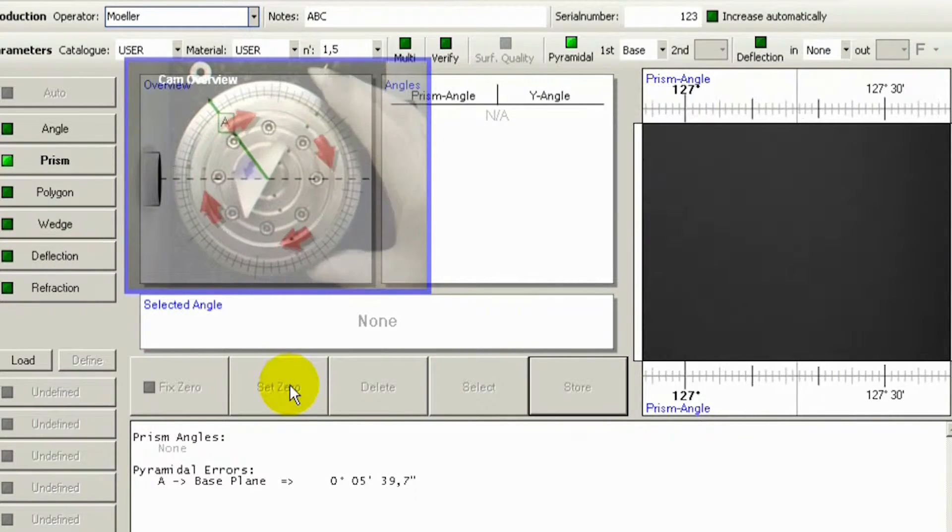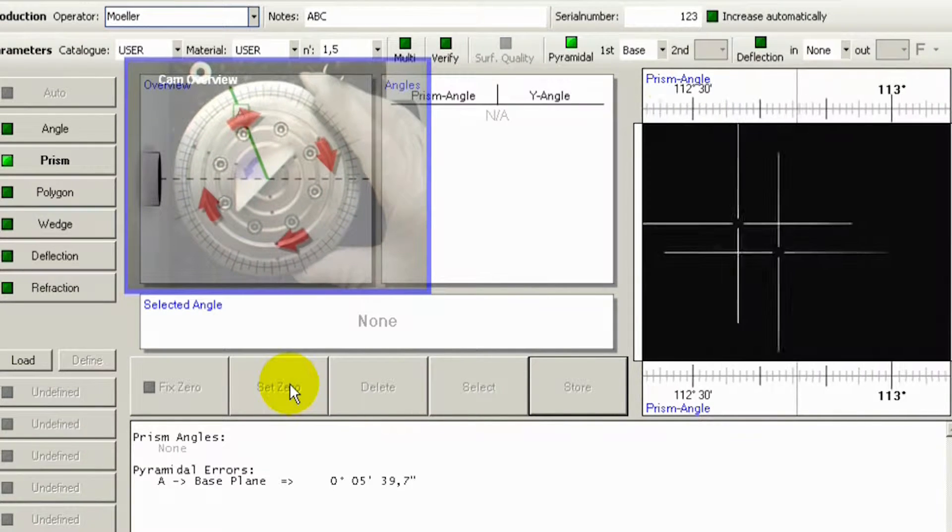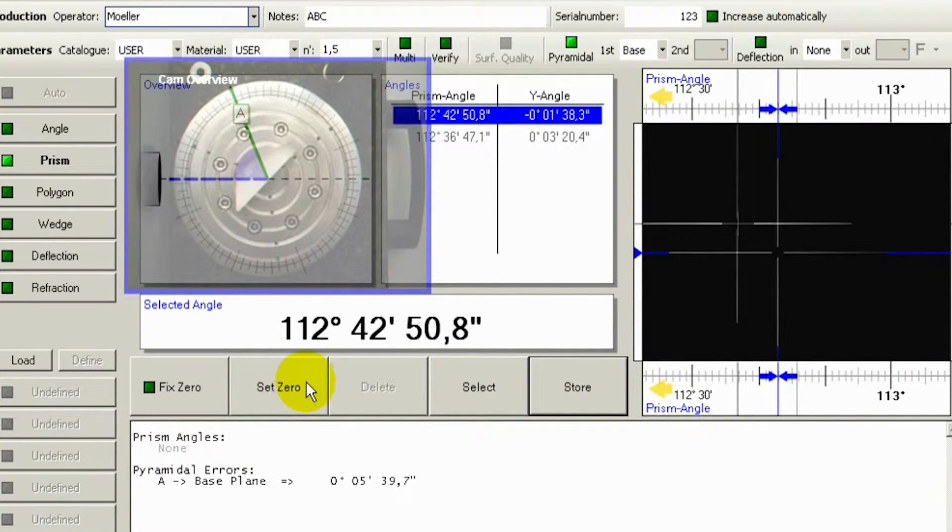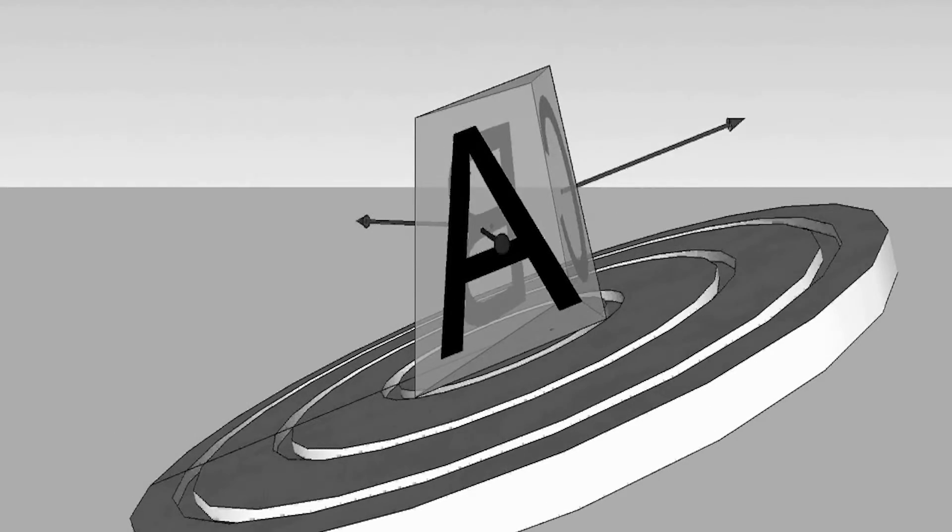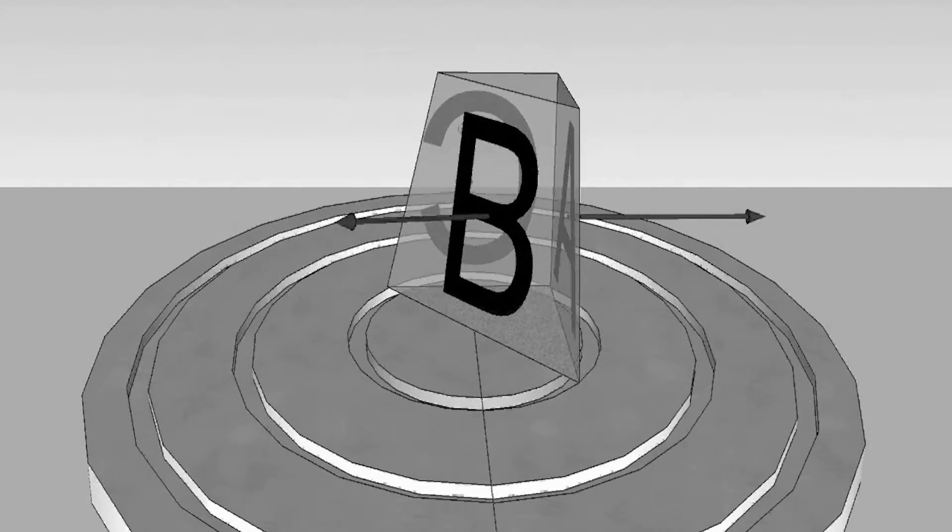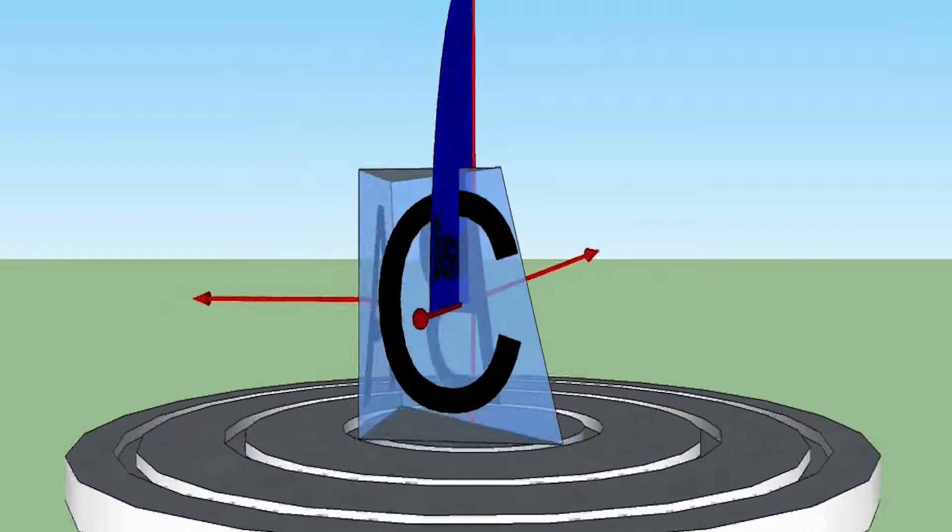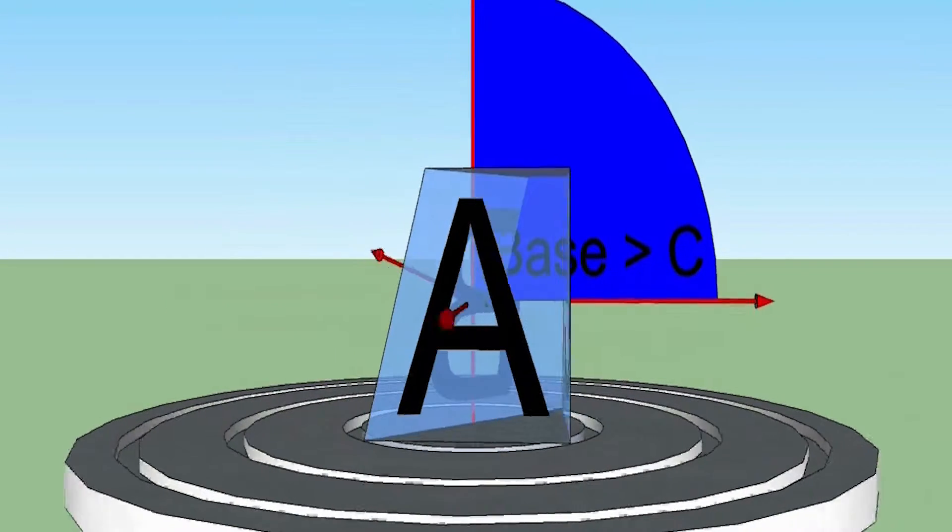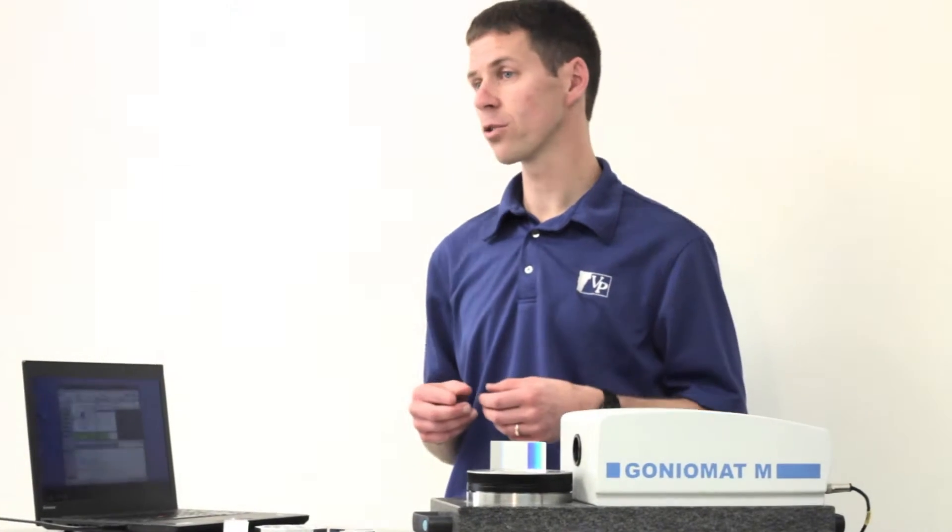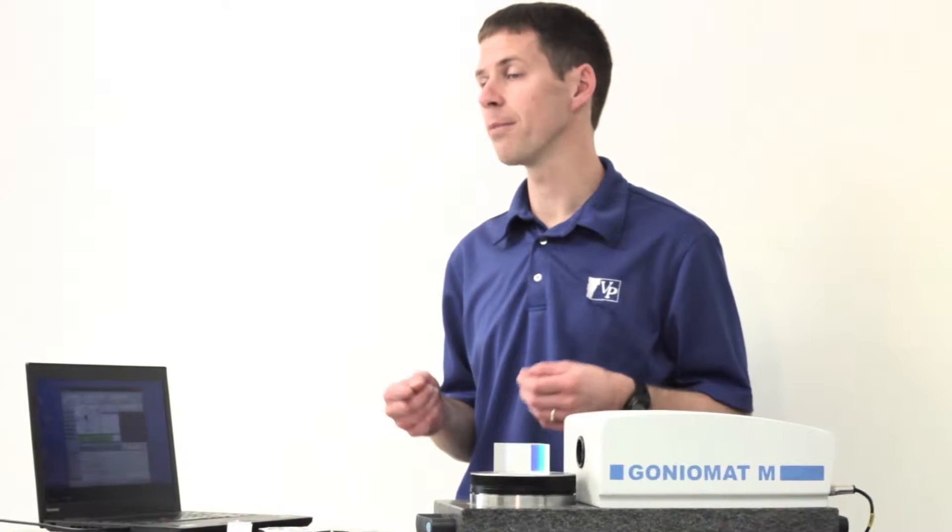The powerful GoniMATIC software integrates a rotary table and an encoder with an electronic autocollimator. GoniMATIC accounts for pyramidal error of your prism or system automatically by using a virtual tilt table and can report the results referenced to whatever desired plane you want to use. GoniMATIC can also report the results as prescribed in common ISO standards.